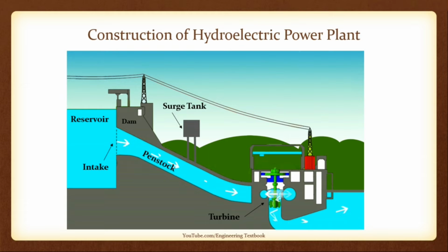Turbine. A hydraulic turbine converts hydraulic energy into mechanical energy. It consists of a wheel called a runner, provided with a number of curved vanes on its periphery, and a guide apparatus to drive the flow of water at the inlet of the turbine in a specific direction. A hydraulic turbine can be set horizontal or vertical. The factors considered are cost, type of turbine, building space, plant layout, etc.